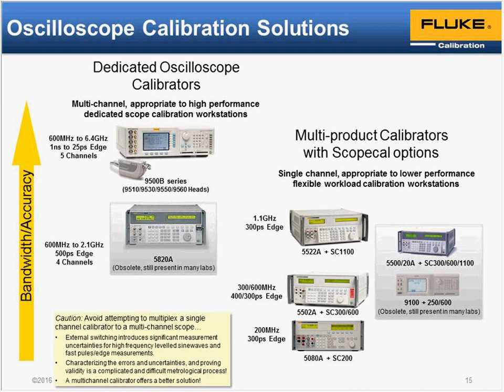You will see instruments like the 5820 multi-channel calibrator and the 5500 series, and even some of the 9100s being worked on in the labs. And the principles and practices we're talking about here are equally applicable to any and all of those.